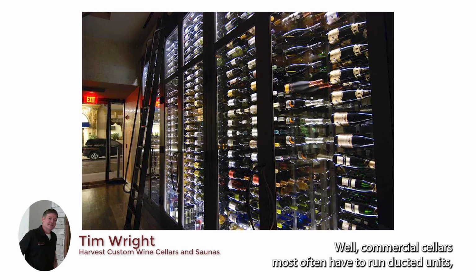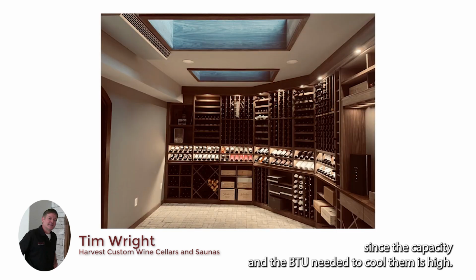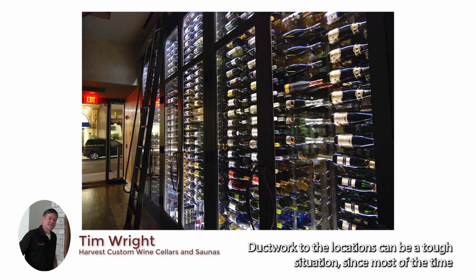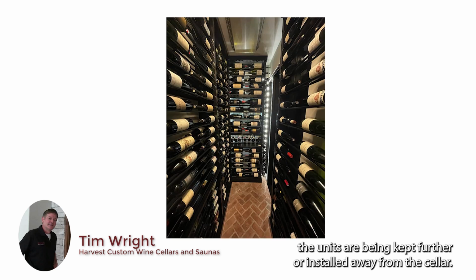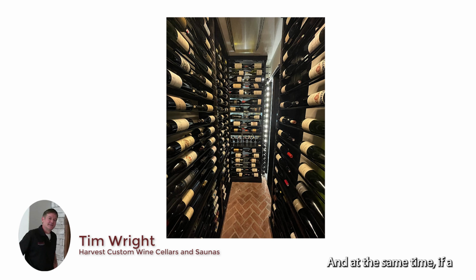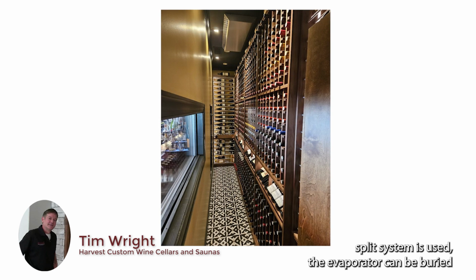Well, commercial cellars most often have to run ducted units since the capacity and the BTU needed to cool them is high. Ductwork to the locations can be a tough situation since most of the time the units are kept further or installed away from the cellar. And at the same time, if a split system is used, the evaporator can be buried and make it difficult to service in the future.